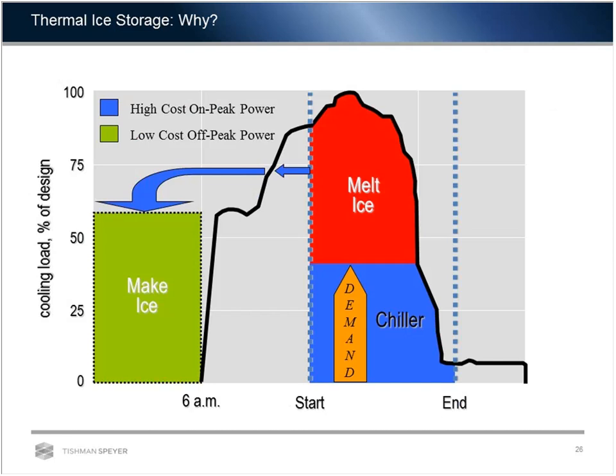The blue chiller portion shows small chiller usage during the hottest days outside in a partial thermal storage system, otherwise the amount of ice you would need in a full thermal storage system would be tremendous.